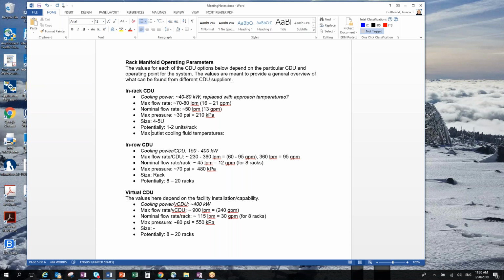The point being, in my view, another way to think about this: when I go about designing a manifold, I don't think about the CDU at all. I think about the IT equipment that the CDU needs to support, and that's how I design my manifold. The CDU is an afterthought — now I need to find a CDU that can provide enough flow rate. But I need to build and size the manifold to meet the demand of the IT equipment, not the demand of the CDU. Again, it's just a different way of thinking about it. I'm not saying one is better than the other.